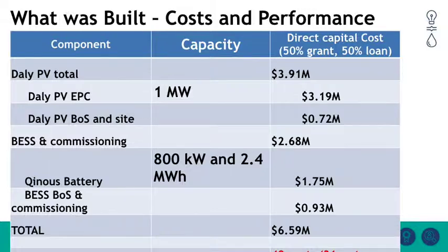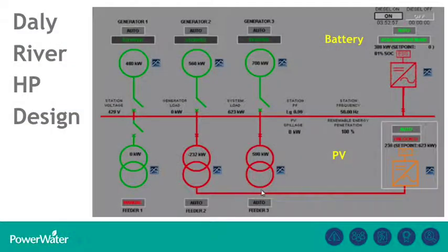Okay, this is our HMI view of our typical power system. On the left there, typically 3 generators, typically 3 feeders. Normally they're all in operation, but this screenshot was taken when one of the feeders was being serviced. The PV is connected through the HV network, an 11 kV distribution network. The icon to the top of the PV is the battery system connected to the LV bus inside the power station.